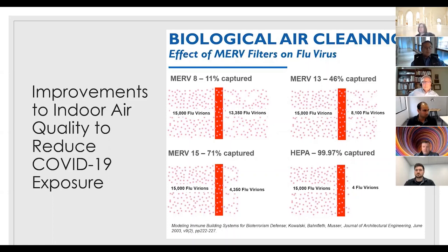Now please understand that COVID-19 and many other viruses are way too small to be captured by MERV filtration. Where you are effective is when these molecules attach themselves to other airborne particles, which can be caught in the filters. HEPA filtration is of course the most effective, but most of our commercial building systems can't handle the pressure drop caused by HEPA filtration. Also, as you increase your MERV filter ratings, you have to be careful for that pressure drop and the ability of your mechanical systems and fan motors to effectively deliver air through the space through those higher rated filters.